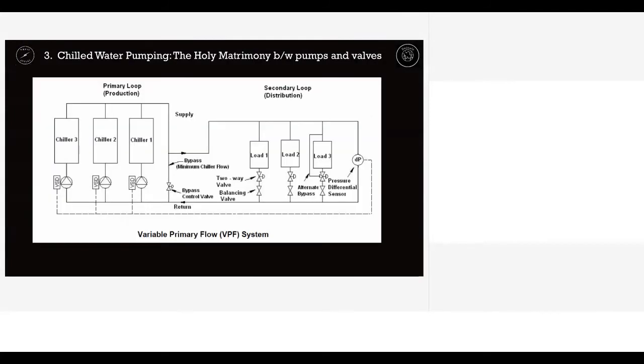So this is what I told. This is a chiller plant layout. There is a VFD on top of your chilled water pump, this is your supply, and this is your load. If this is a region that is shutting down, imagine this is the dietary AHU or the canteen AHU that I showed you in the slides before, shutting down at 7 o'clock in the evening. This is a motorized valve that is integrated with the IoT BMS. It will sense that this area is off, and the IoT will give the command for this valve to close. That will increase the pressure of this water line from 0.5 to 0.8 to 1 or 1.2 kilogram per cm square. That will be identified by the differential pressure transmitter, which gives feedback to my pump, and I will ramp the frequency down. So this is how we save energy in chilled water circuits in a centralized air conditioning building.